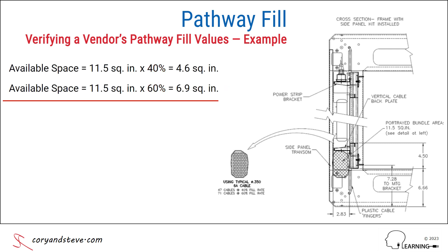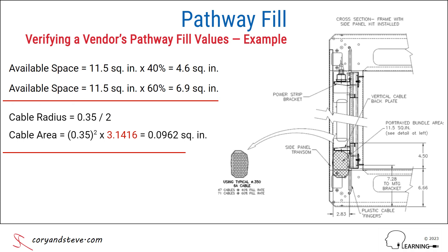Next, we calculate the individual cable area, first by taking the cable's outside diameter and dividing it by 2 to get the radius. Then, we square the radius and multiply by pi to get a 0.0962 square inch area per cable.